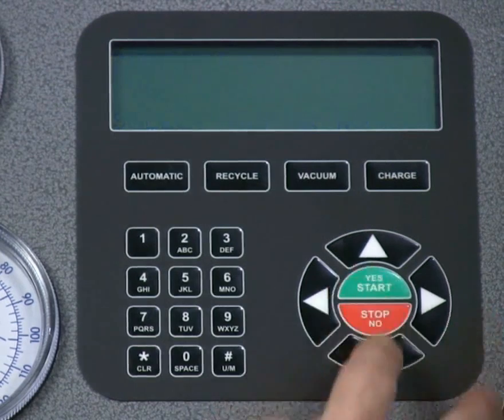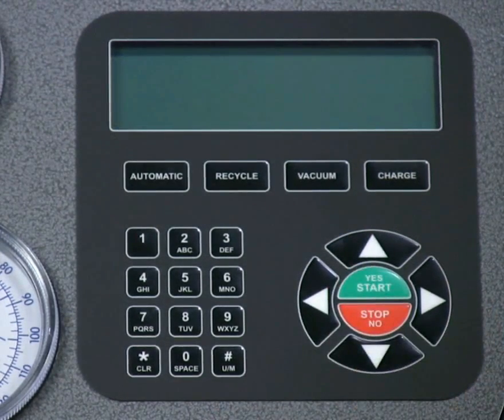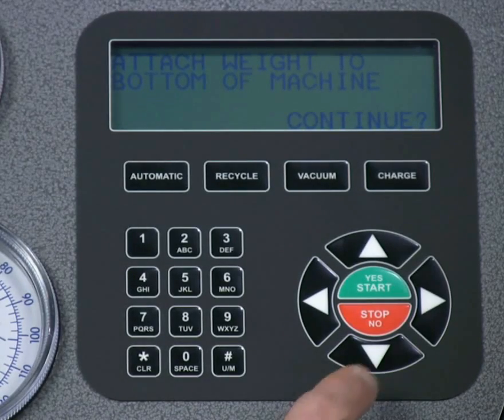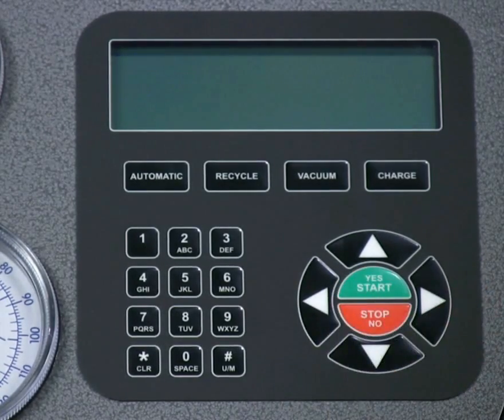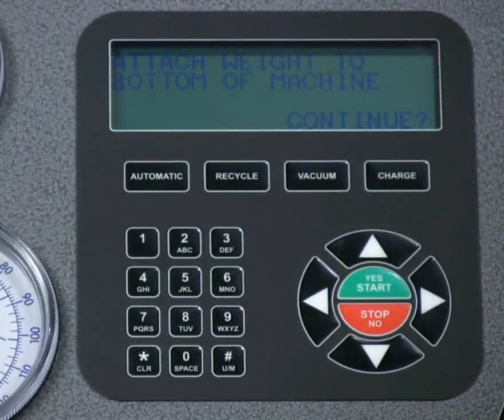Press the green Yes button. A blank screen will appear for about 30 seconds while scale stability is evaluated. This is normal. Please be advised, you need a minimum of 2 pounds of refrigerant to check. To begin, press the green Yes button and retrieve the calibration ball from the storage pocket. The RHS980 will prompt you to attach the calibration ball underneath the machine.